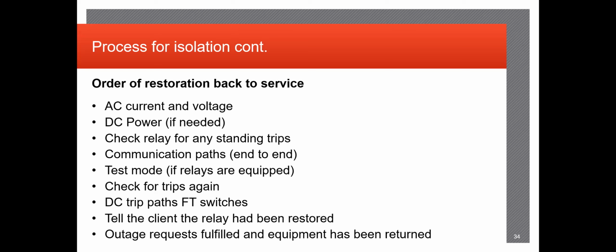And then the order of restoration is fairly important as well, because you need to do pretty much the complete opposite order back. So you want to start with your AC current and voltage sources, powering it back up. And then the biggest key factor is, once that relay is powered up and it's reading AC current and voltage sources that should be from an energized circuit, you'd want to go into the relay and verify if there are any standing trips. You don't throw any of the test switches in to continue, because that could cause an inadvertent trip. You want to identify why there would be a standing trip, what it could mean, why it's there, and troubleshoot until it's been resolved, and then continue on with your restoration process.